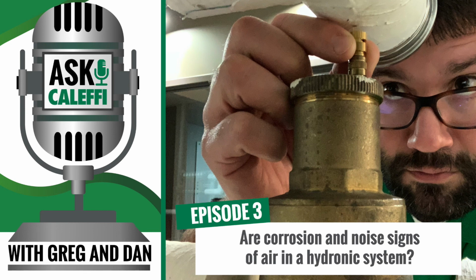But you've got to remember, once they're lifted into place and the system is filled with however many gallons of water these take, we've got the chart here, you're looking at an additional 8 pounds per gallon. Right. And they have pretty good internal capacity, so that's going to add a lot of weight to the system. The unit itself, we'll say a 2-inch, has a dry weight of 34 pounds, but it can hold up to 2 gallons of water. So you're going to add some additional weight. So no, you're not going to want to hang off of those eye hooks.